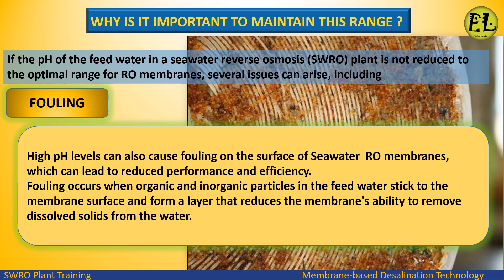Fouling: high pH levels can also cause fouling on the surface of seawater RO membranes, which can lead to reduced performance and efficiency. Fouling occurs when organic and inorganic particles in the feed water stick to the membrane surface and form a layer that reduces the membrane's ability to remove dissolved solids from the water.